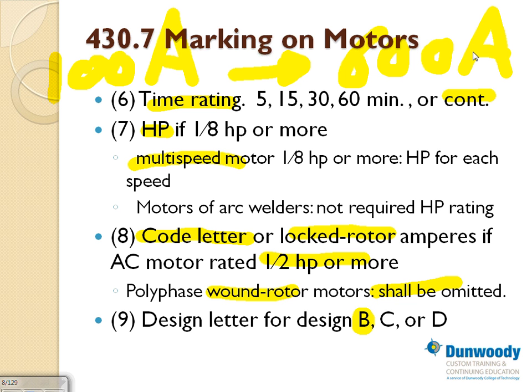For example, some motors have very high starting torque. If I want to start something with a high starting torque, or a low starting torque, or variable torque, electrically speaking, we care less. Mechanically speaking, if you put high starting torque on equipment, you can shock the equipment and break it into pieces, right? You pull something so hard, if it's too heavy, you can shock it and break it to pieces. So this becomes a big deal. Most of you guys are in the building industry, right? We're in the building maintenance industry. Most of the time we're in design B. Design B has a medium starting torque, medium inrush, so it is good enough for starting the equipment and good enough for running the equipment.